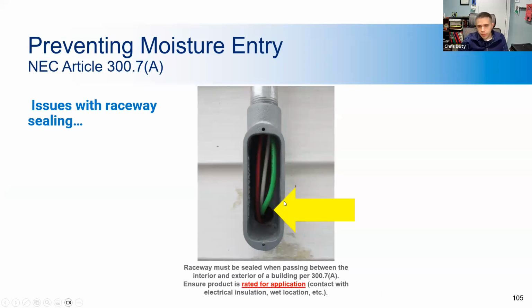Here we have conduit passing from the outside of a building to the inside of a building that was not sealed. You would want to seal that with some kind of insulation. This not having that sealed has a potential for condensation to build up where warm building air meets the cooler outside air, or vice versa. And once that condensation forms, it has no place to go but down the conduit into the panel board, or whatever's on the other side of this wall. So again, you want to put some kind of insulation in there so that the indoor air and the outdoor air don't mix. And this is a violation of the National Electrical Code and of the energy code, since there's an energy component to it.